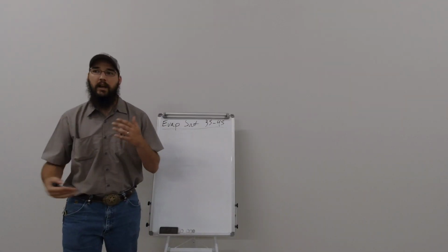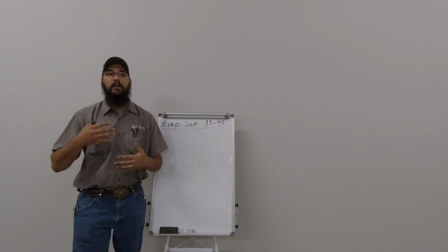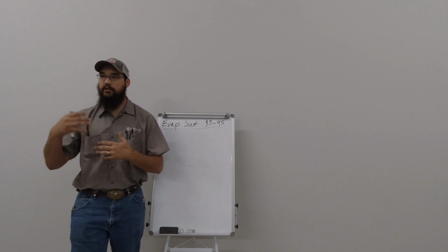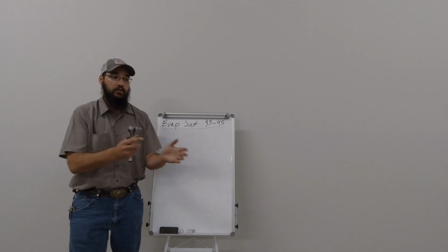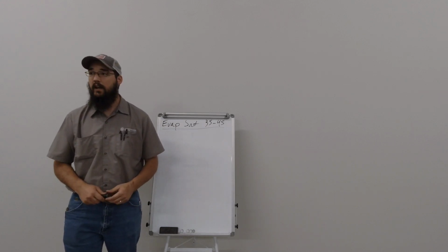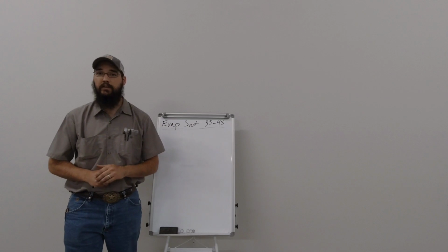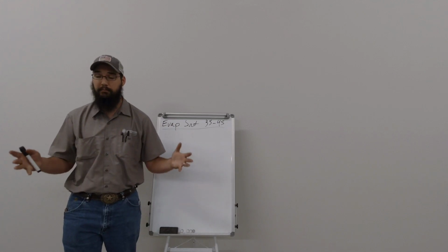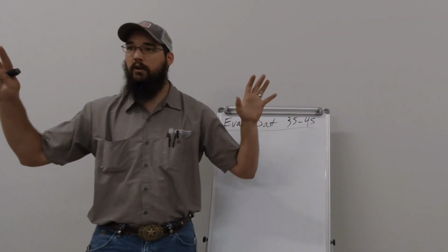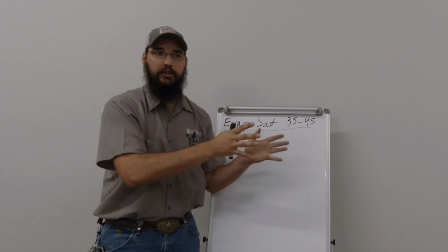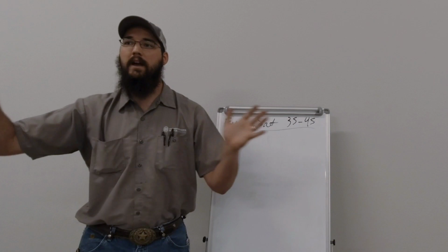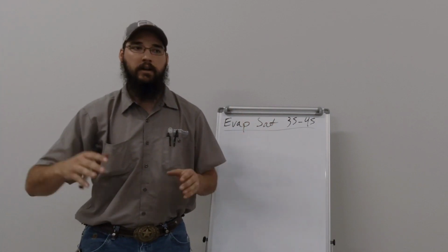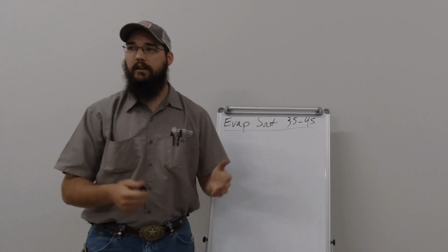And people that get hung up on the pressures, just from experience, tend to struggle with understanding the system, especially if they're used to seeing 410A every day, and they walk over and see a 407C system that's got a glided blend. People's minds start blowing. But if you understand saturation and get away from just relying on the pressure, it doesn't matter what you walk up to. It doesn't matter if it's got a glide or not. It is what it is.